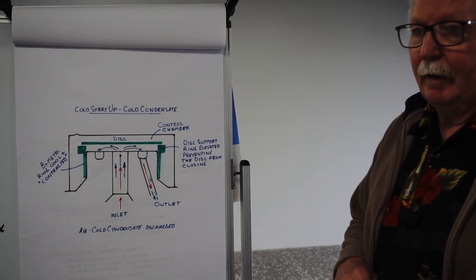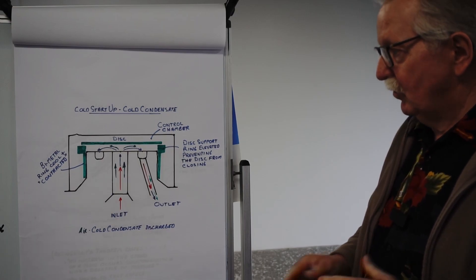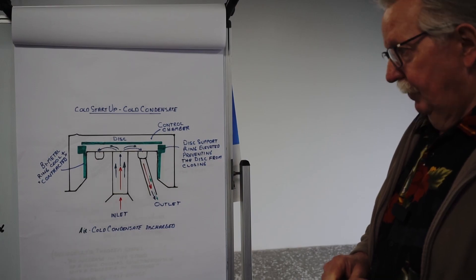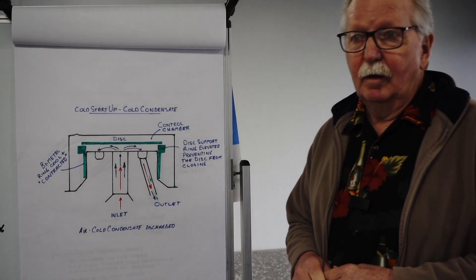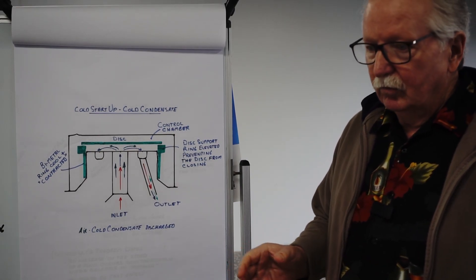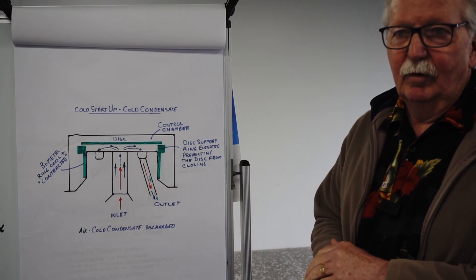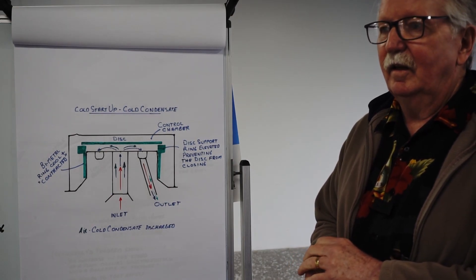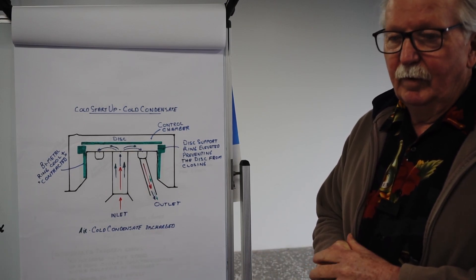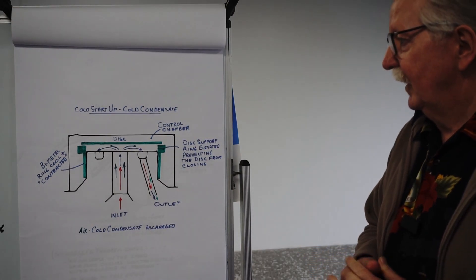They don't like a lot of back pressure—maximum permissible back pressure usually around 50-80 percent of the incoming pressure. Some thermodynamic types are available with anti-air binding discs. Not all TDs have them and they don't necessarily always need them, but it's a newer invention and it does have its benefits, which we'll talk about later.